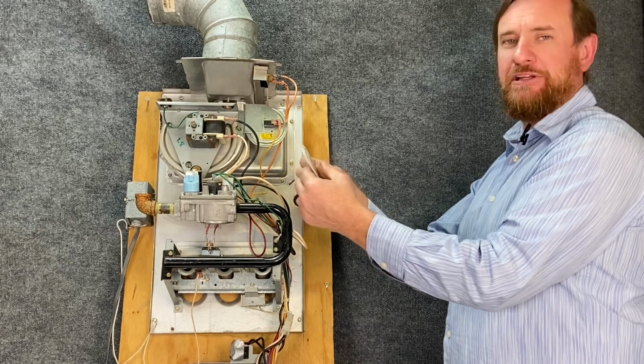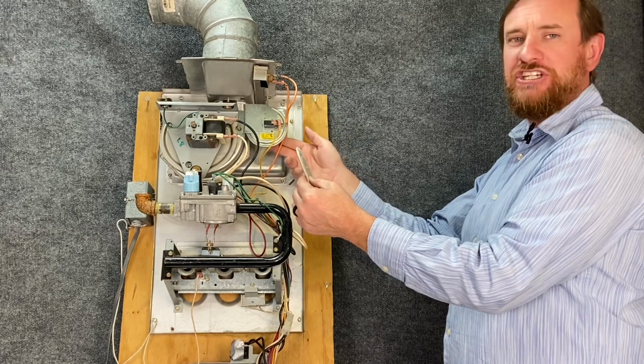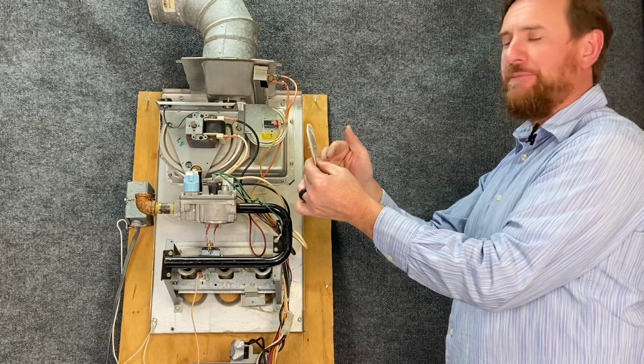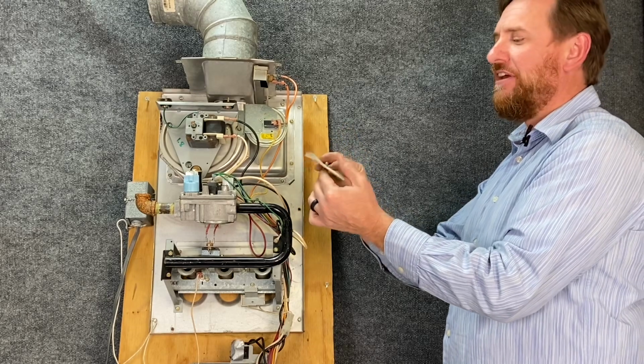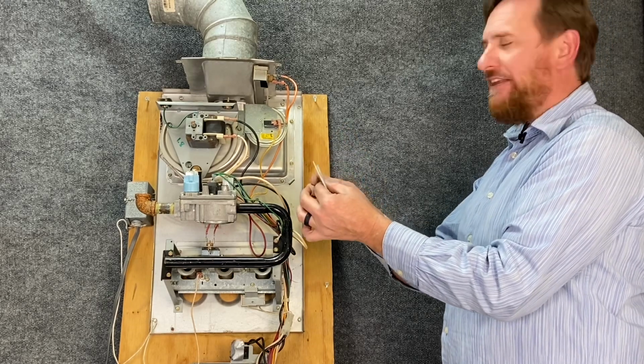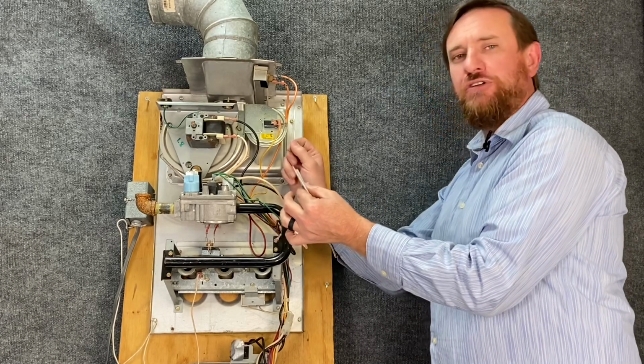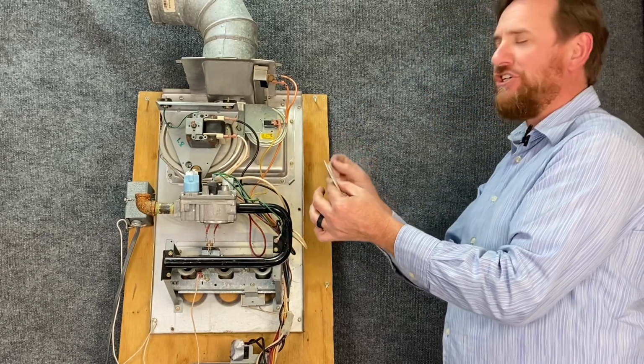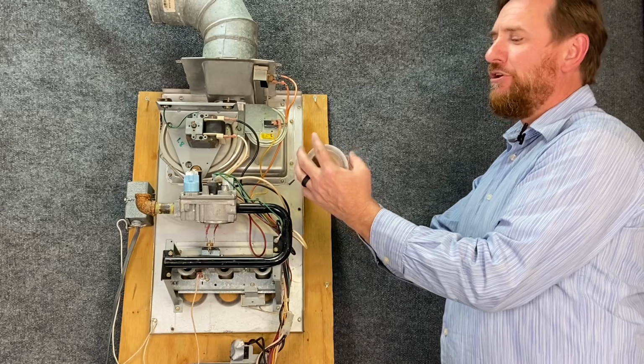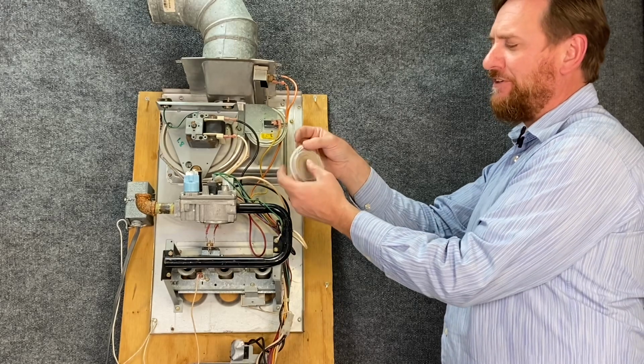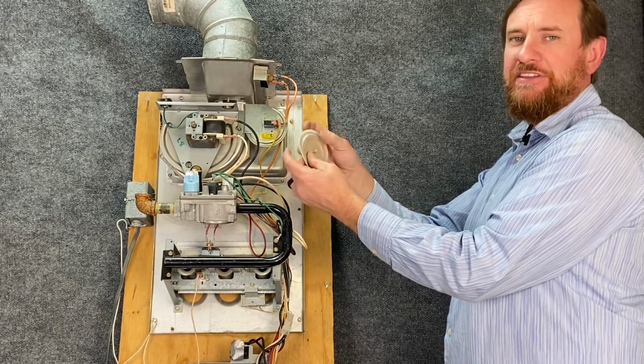They can crack, they become brittle, especially if you have condensation in there, which you shouldn't have. That can build up in here and cause severe problems with these. It's important that when you're checking this, you don't put your mouth to that tube and suck on it. I've seen people check them like that, but the problem is you pull too hard and it does what happened to this one. It actually rips this diaphragm.